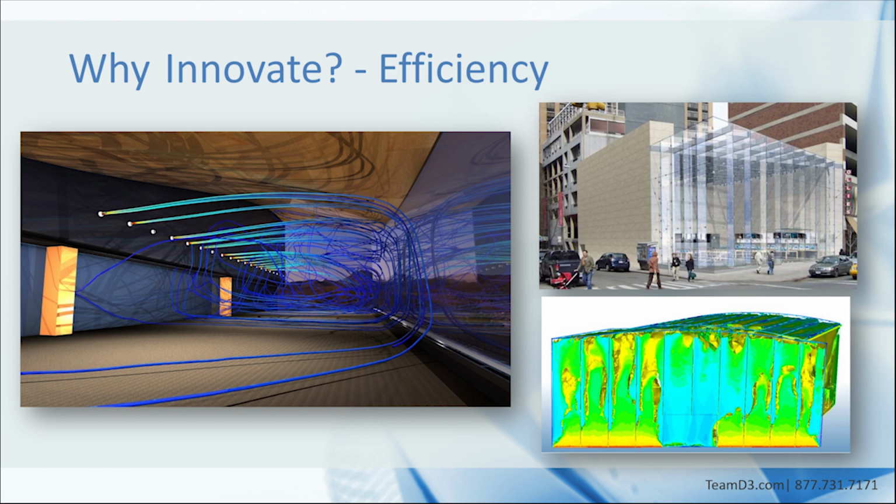They were naturally very concerned that additional ceiling diffusers would be needed, but that was aesthetically not an option. Over a period of several weeks, 40 different variations were simulated, and an ideal configuration was selected. Without CFD, specifically Autodesk CFD in these cases, this would not have been possible.